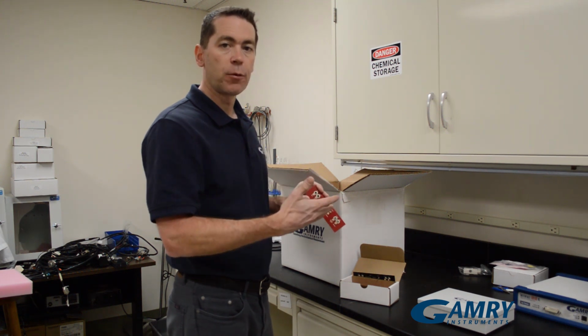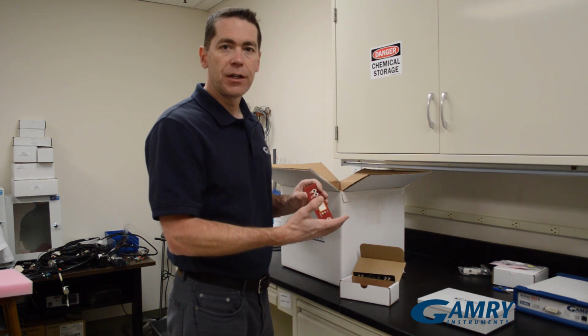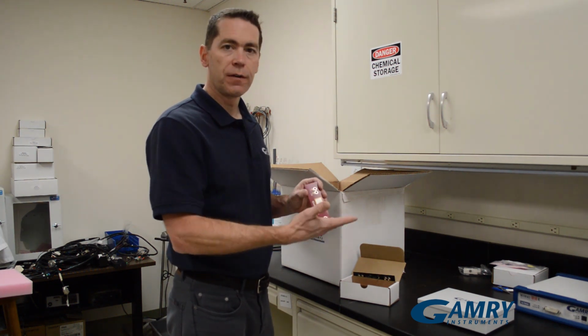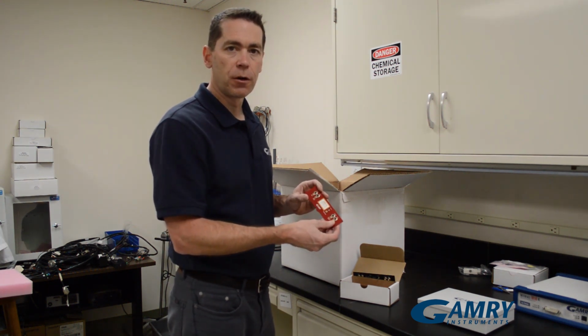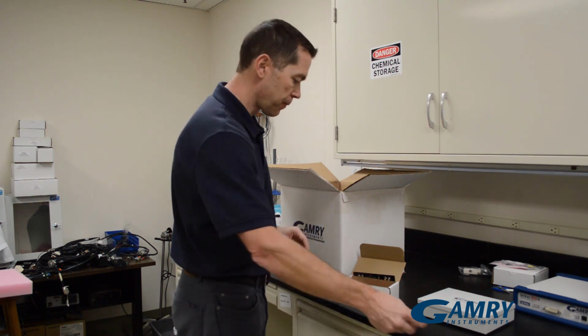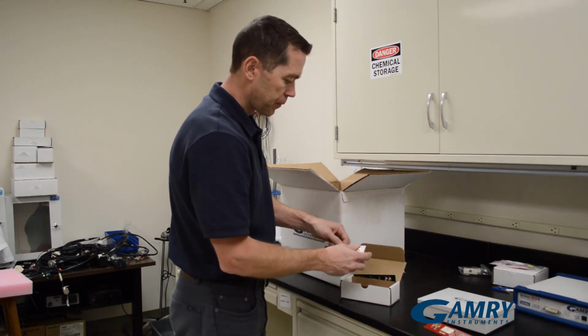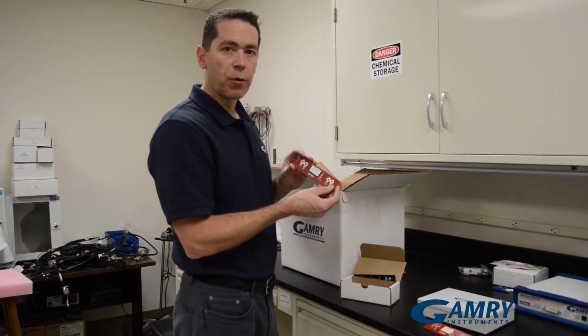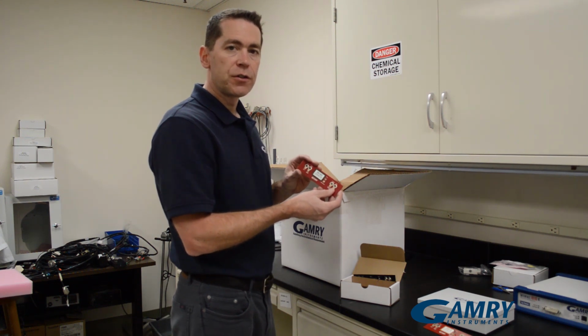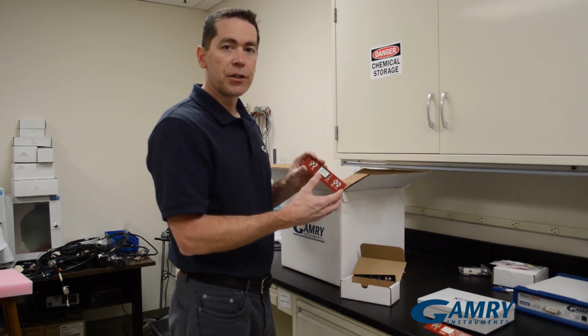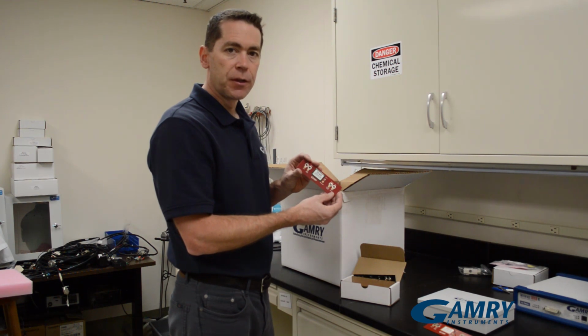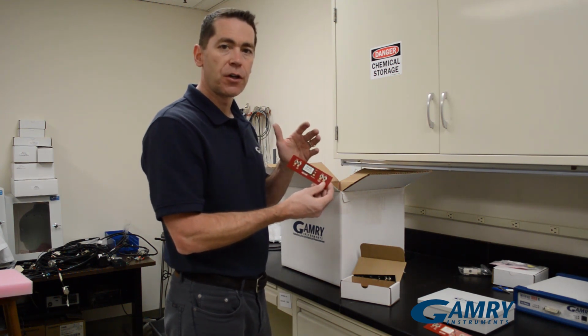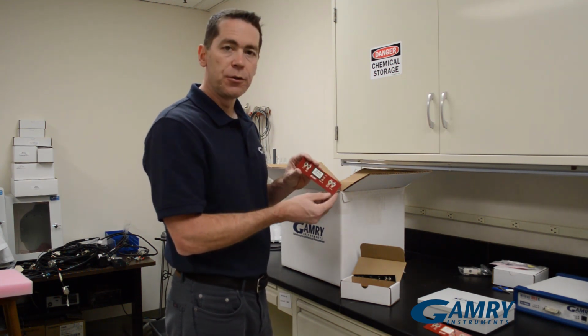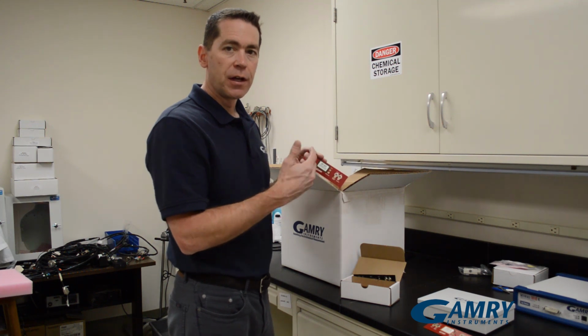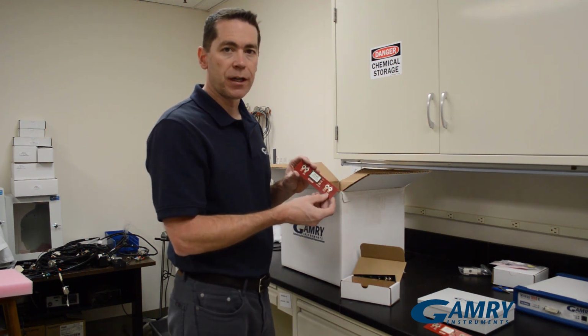You use that to calibrate your instrument once a year, or if you change the laboratory environment, or if you suspect something might be wrong with your instrument, you would run a calibration. We have a 20 kilo ohm calibration cell, which is used for a cable correction calibration. So if you're testing any high impedance coatings or something like that, you would use this as a calibration in addition to the normal user calibration.